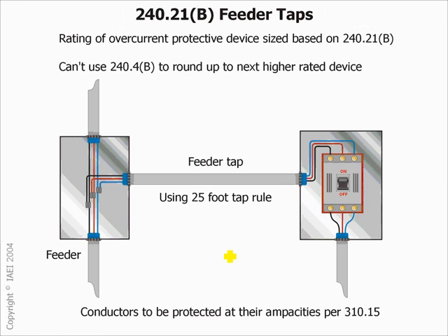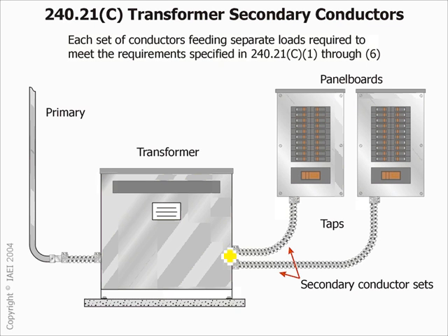So that's your conductors. Feeder tap 25 feet. We talked about the rules of feeder tap. Each set of conductors, when you get a feeder tap like this, guys, that was changed in 2011. Now, the same thing, when we tap for transformers, there's a rule that says both the primary and secondary cannot be more than 25 feet. That rule, 25 feet or 10 feet. So if you put your panel 10 feet from the transformer, you don't have to have an overcurrent protection device right at the secondary, and you can depend, as we always do, on the panel main to be used as the secondary overcurrent protection device.